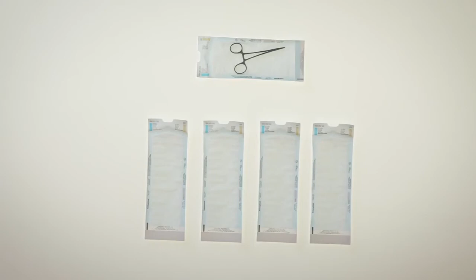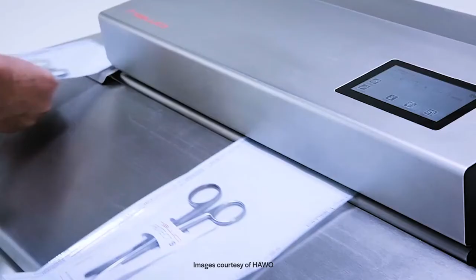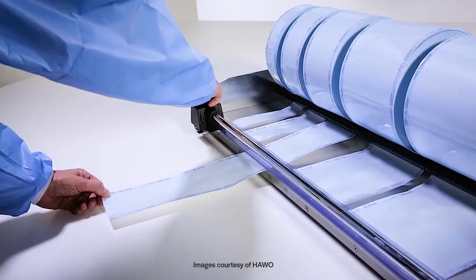Rolls. If this format is preferred, introduce the product to be sterilized into the pre-cut roll and seal the two ends with a sealing machine. If this type of packaging is chosen, it's important to point out that we need a dispenser that previously cuts the roll to the desired length. The widths are all standard, but the length is determined according to the dimensions of the product inside.